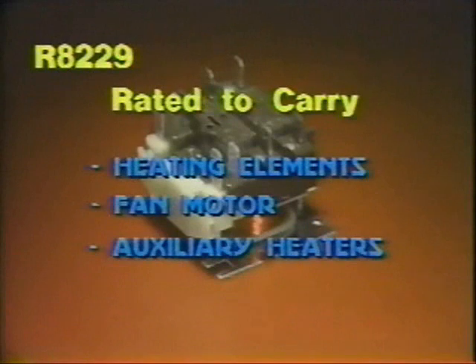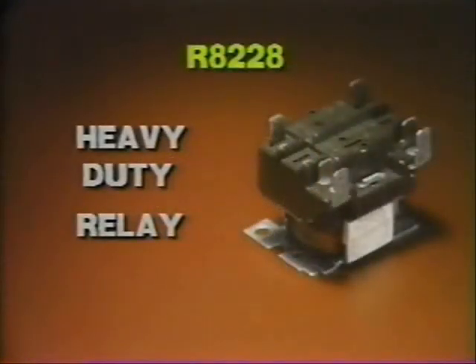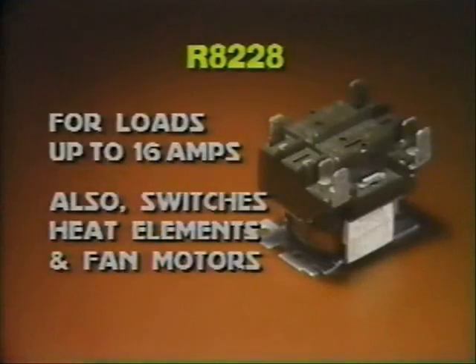The Honeywell R8229 electric heat relay is rated to carry the combined load of the heat elements and the fan motor. This versatile relay can also switch auxiliary heaters and heat pumps. Honeywell's R8228 is a heavy-duty relay rated to switch loads up to 16 amps. It can be used to switch electric heat elements or large fan motors.